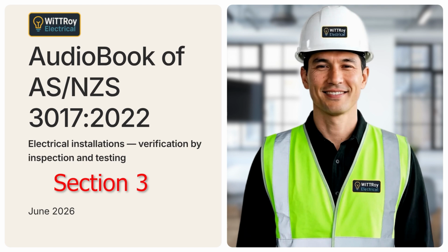The general condition of electrical equipment must also be checked. Look for signs of damage that could affect safe operation. Also check that unused electrical equipment has been properly disconnected where required. In simple terms, the general inspection asks, is the installation safe to touch, safe under fault conditions, protected from hazards, protected against fire spread, and in good condition?